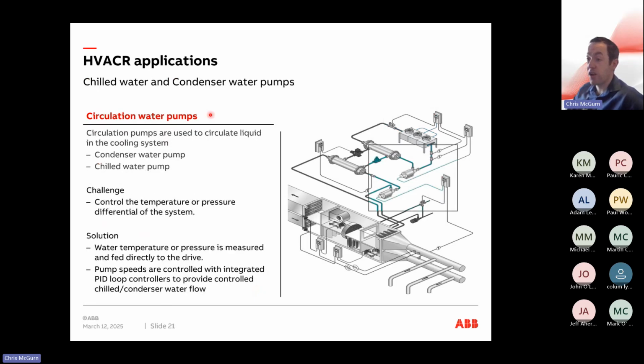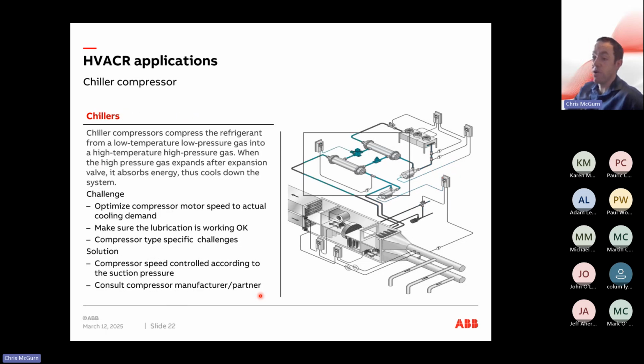Here's another one, a circulation water pump. And what does it need to do? It controls the temperature or pressure differential of the system. How can VSDs help? The water temperature or pressure is measured and fed directly into the drive. So again, sensors can be fed into the drive, and the pump speeds again can be controlled with PID loop controllers, giving feedback and telling it when to speed up, when to slow down.